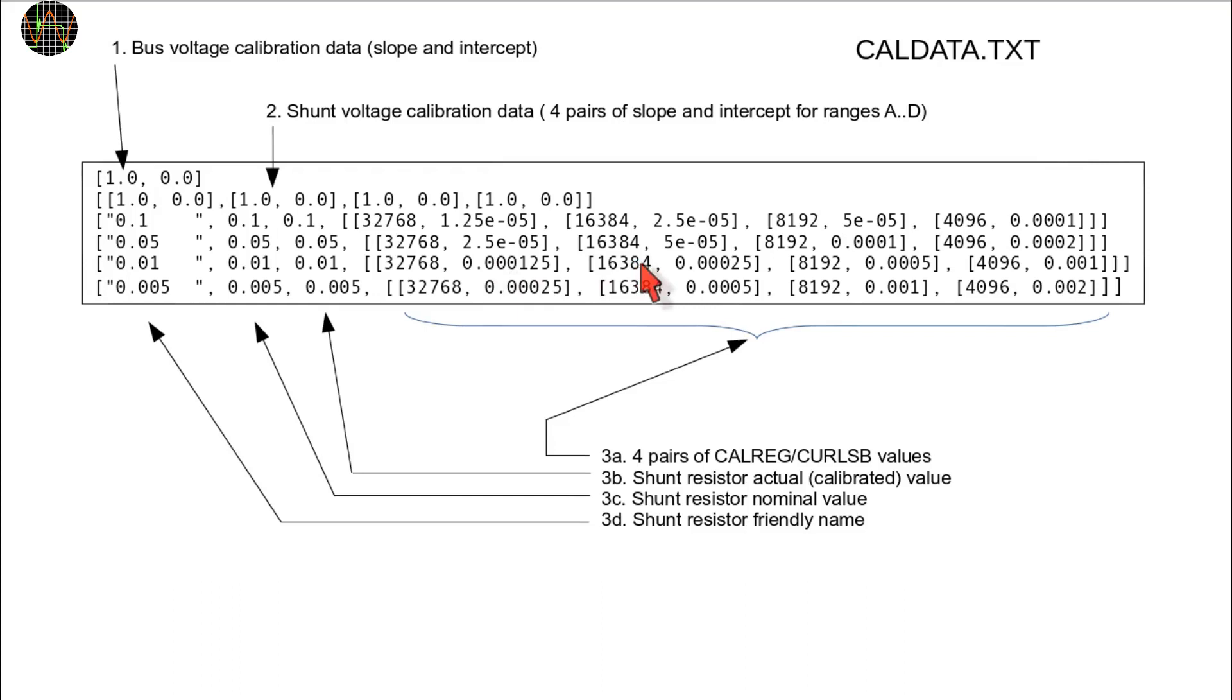Another time saving thing you could do is just performing the shunt voltage calibration for range D and then edit the Cal-Data text file by hand to copy the D range slope and intercept values by hand into the positions for range A, B and C.